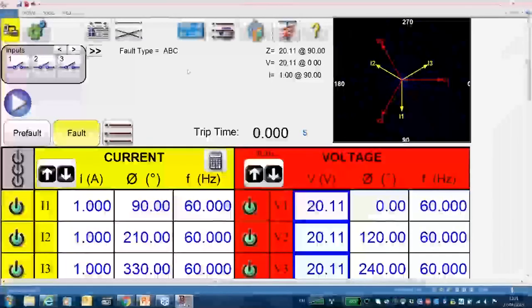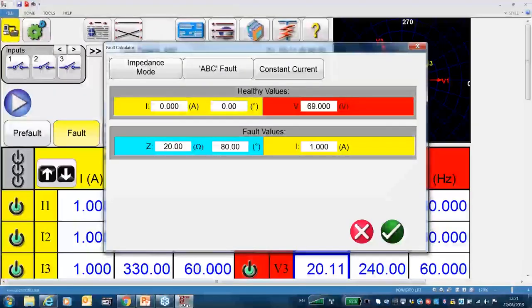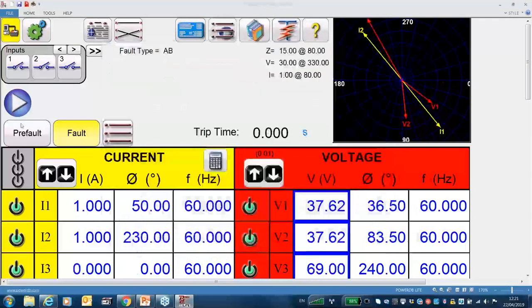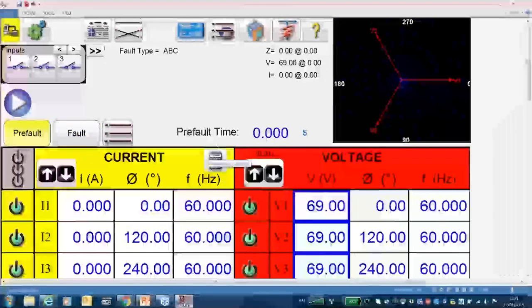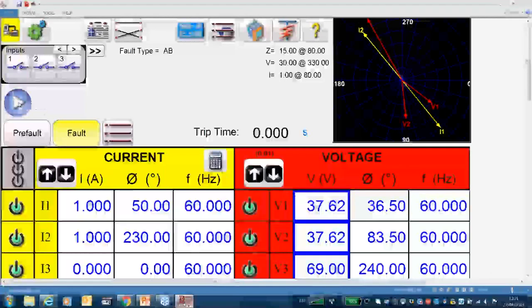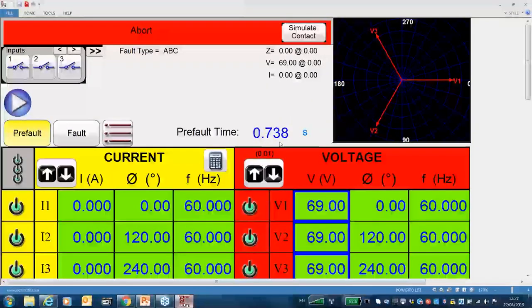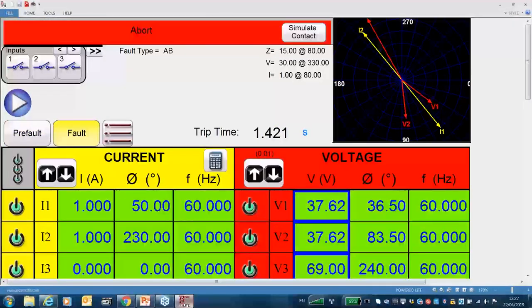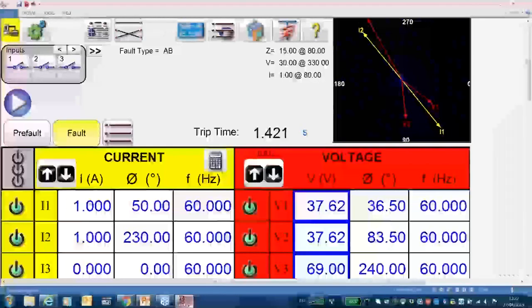For a timing test, go back to the calculator and set the fault — for example 15 ohms — change the fault type to phase-to-phase, set pre-fault timing, and then play. The pre-fault will run for two seconds, after which it goes to fault and gives the correct trip time. From here we can verify zones and whether their settings are correct. This is a quick manual check you can do everything from the Freja front panel — you don't even need a laptop.